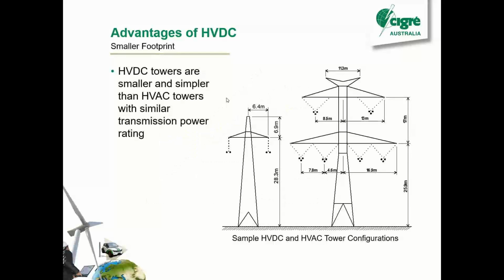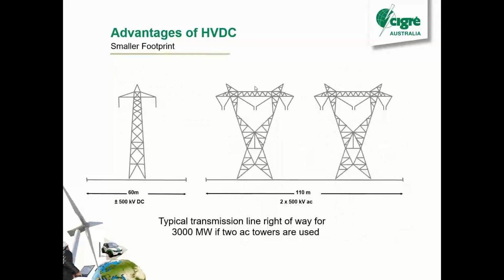One of them is the towers that you need for HVDC. For a given power rating, you can have a much smaller tower and a much smaller right of way. You can see this one HVDC tower with a bipole on it, so you have one pole on this side, one pole on that side. Compared with this double circuit AC tower, it's quite a bit smaller, not as high, not as wide. So you need less land if you're building a new line, less easement, all that sort of stuff. It's just showing that again.